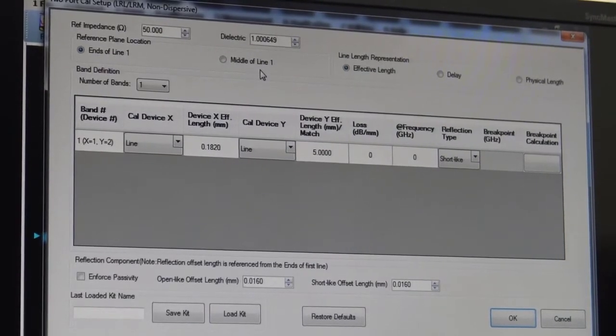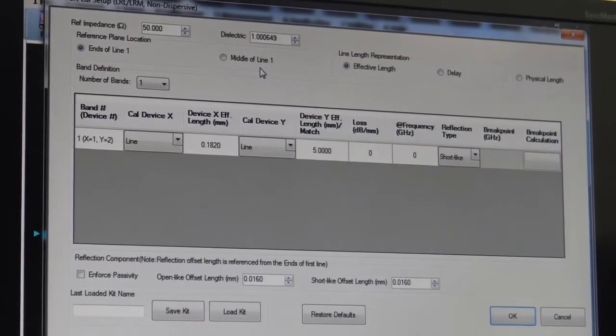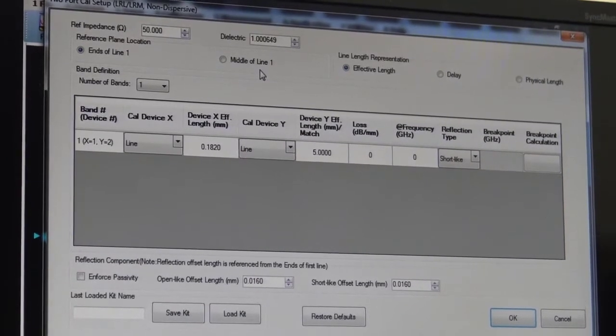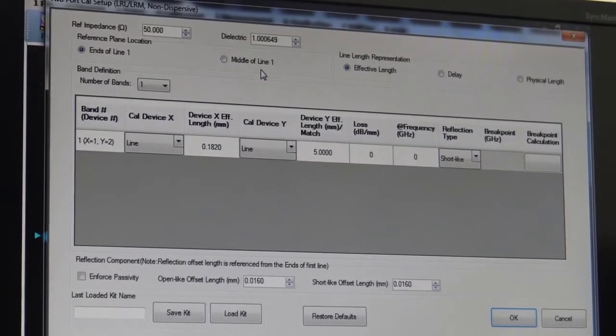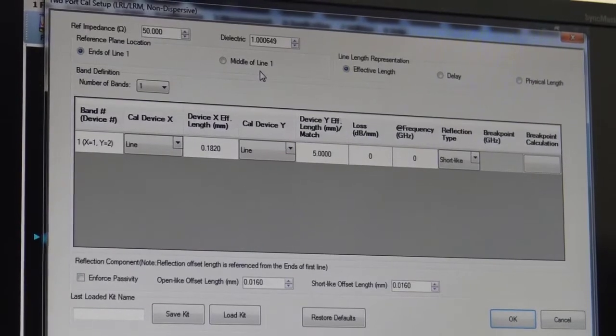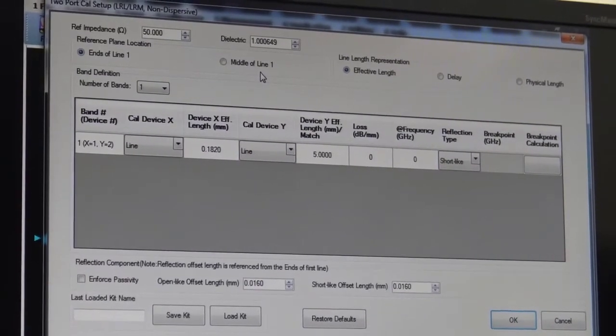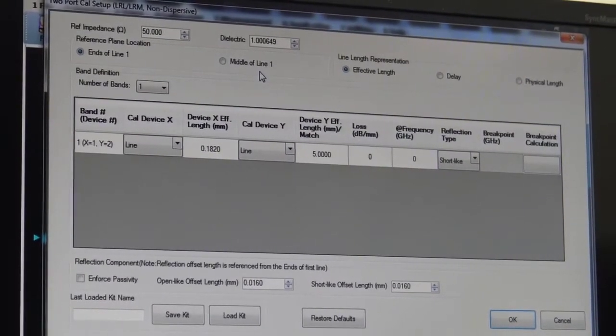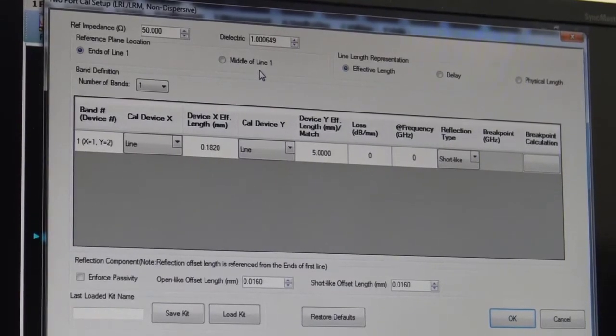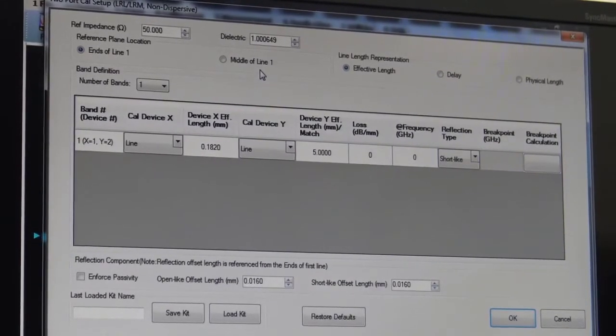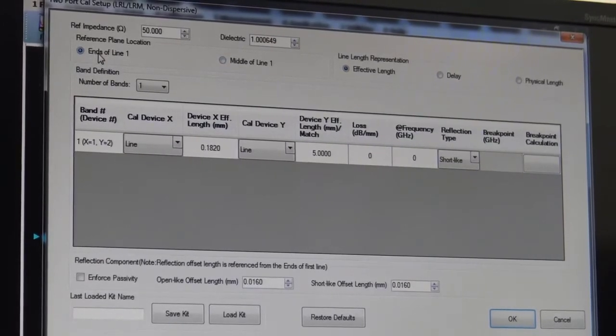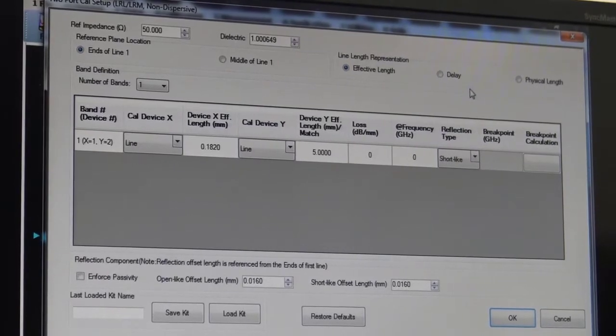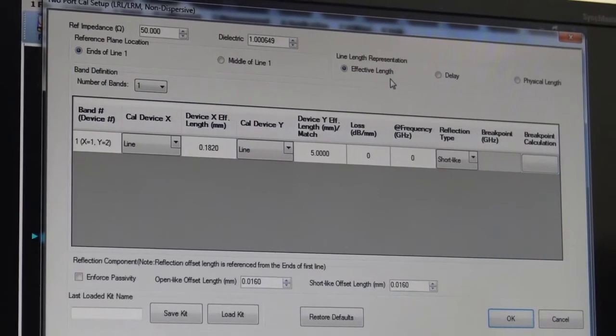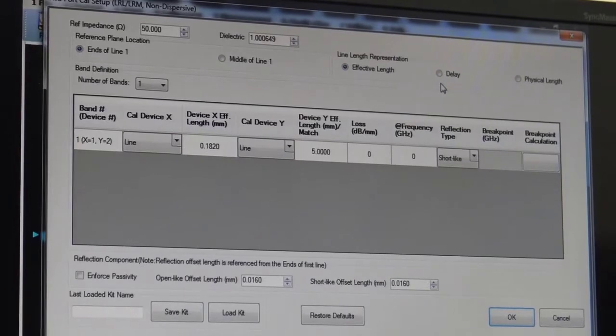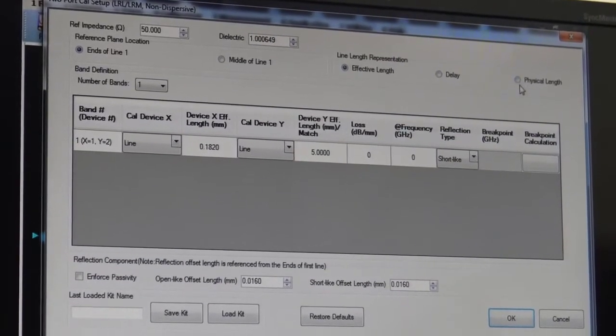In this case, we're going to use end of line, and so now we'll be calibrated at the tips of the probes, and we'll then be measuring everything from the pad along the transmission line to the DUT and include the DUT measurement. So we've selected the end of line here. The length of our calibration through is then defined here either by effective length, by the delay, or the physical length.